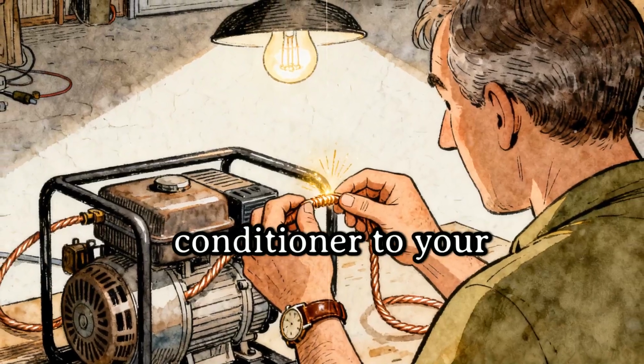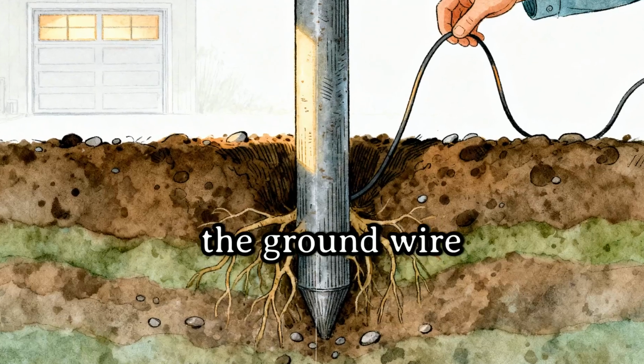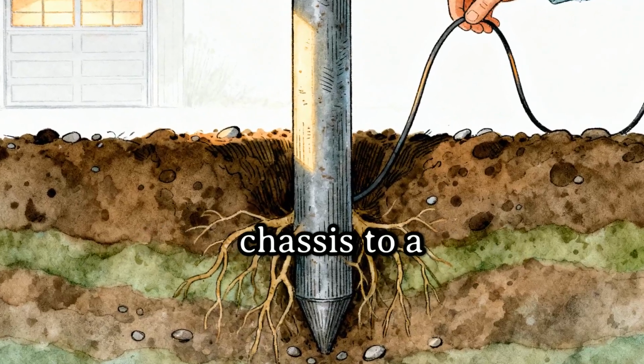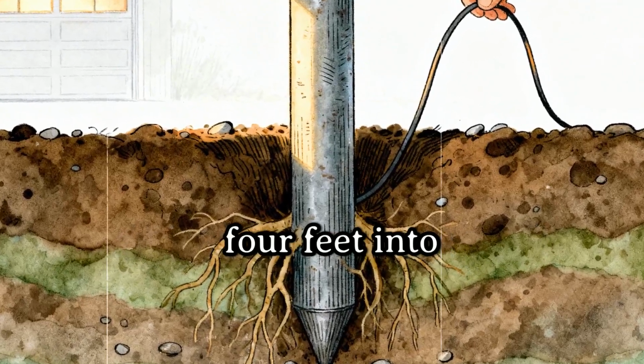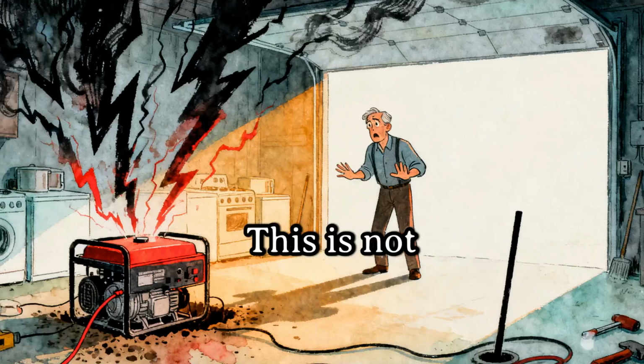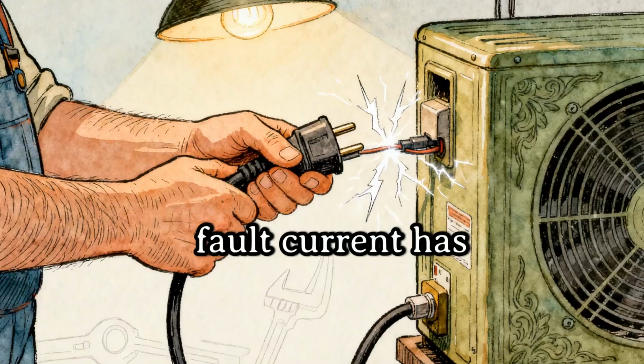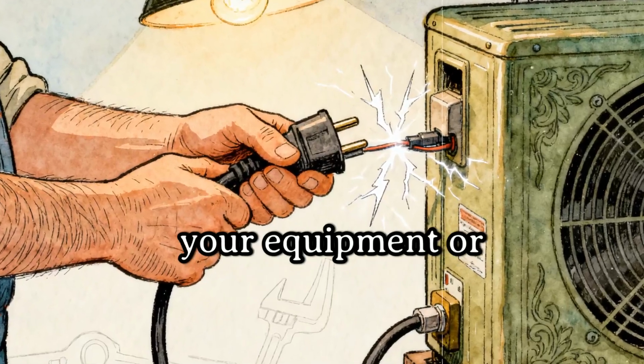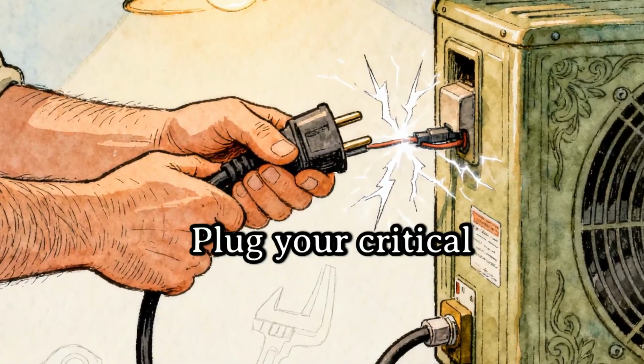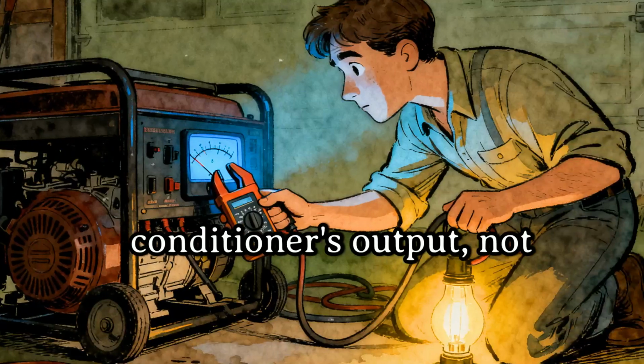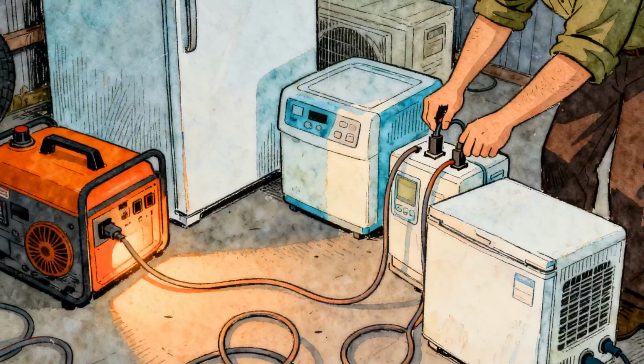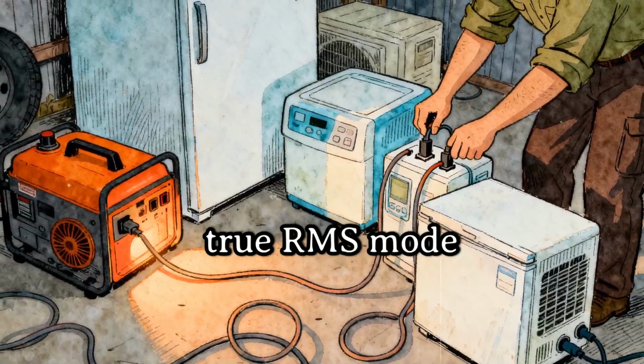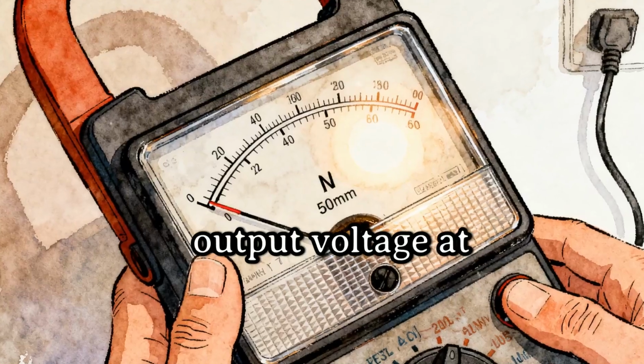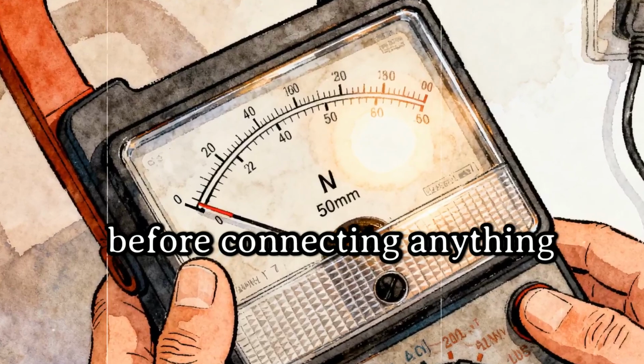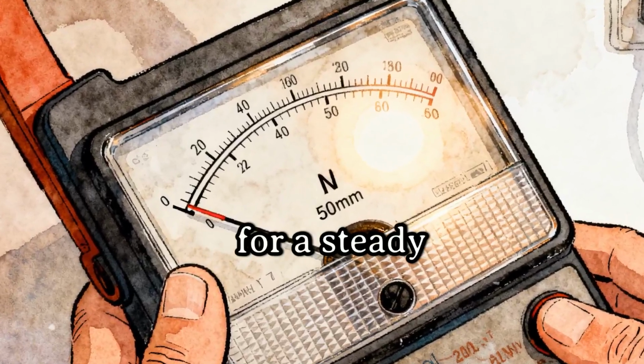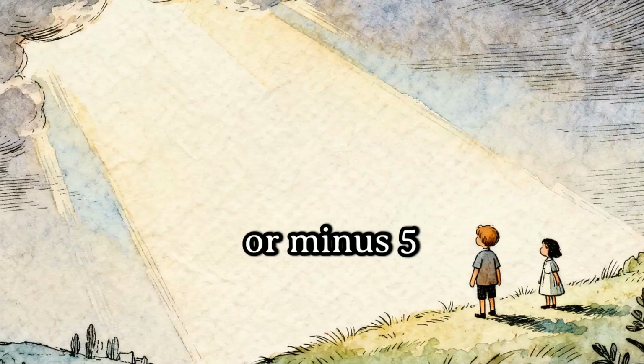When connecting the conditioner to your generator, run the ground wire from the conditioner's chassis to a dedicated grounding rod driven at least 4 feet into soil. This is not optional, and skipping it means any fault current has nowhere safe to go except through your equipment or through you. Plug your critical appliances into the conditioner's output, not directly into the generator. Use the clamp meter set to true RMS mode to read the output voltage at the conditioner's outlet before connecting anything sensitive. You are looking for a steady 120 volts, plus or minus 5 volts.